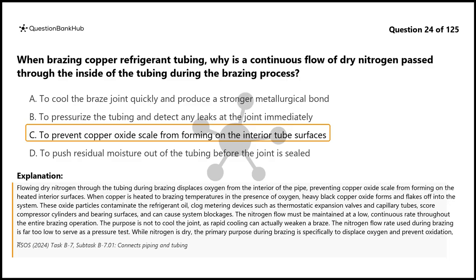The nitrogen flow must be maintained at a low, continuous rate throughout the entire brazing operation. The purpose is not to cool the joint, as rapid cooling can actually weaken a braze. The nitrogen flow rate used during brazing is far too low to serve as a pressure test. While nitrogen is dry, the primary purpose during brazing is specifically to displace oxygen and prevent oxidation, not to remove moisture.